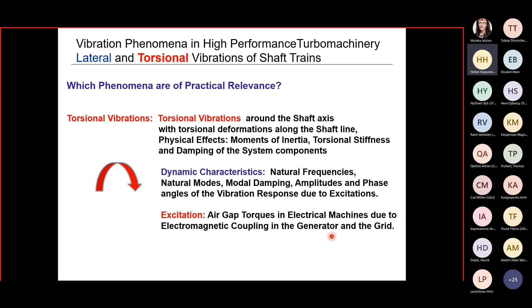And the dynamic characteristics are, again, natural frequencies, now torsional natural frequencies, and natural modes. We have damping. Unfortunately, in the torsional vibrations, damping is very low. That means if something happens and there is vibration, the decay is very low. Furthermore, amplitudes and phase angles, also the vibration response due to excitations, is an important dynamic characteristic. And the excitations are mainly coming from the air gap torques in the electrical machines due to electromagnetic coupling in the generator and in the grid.